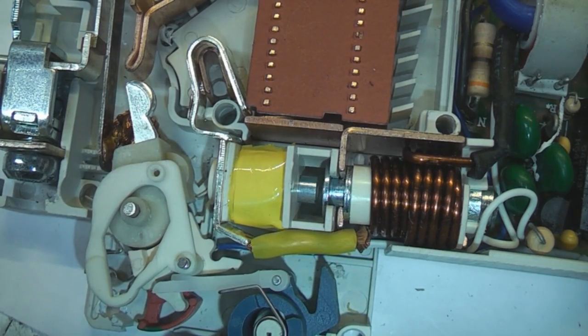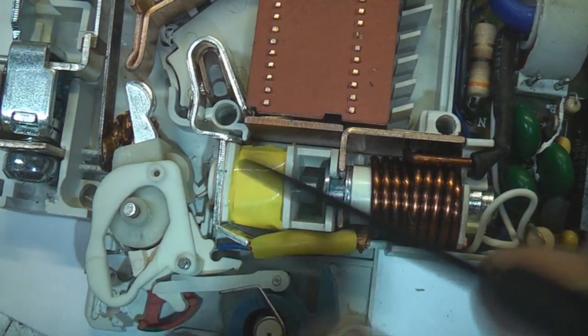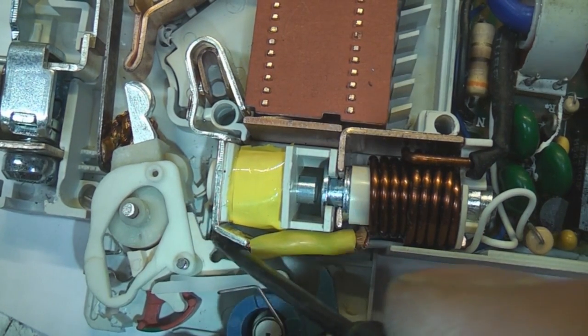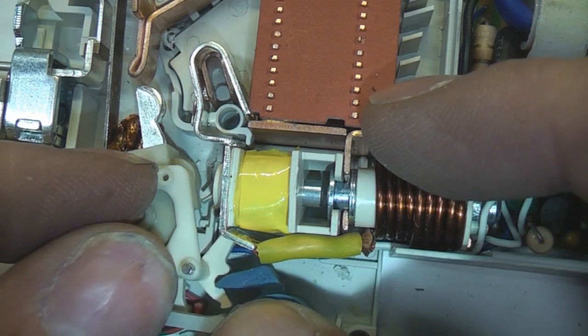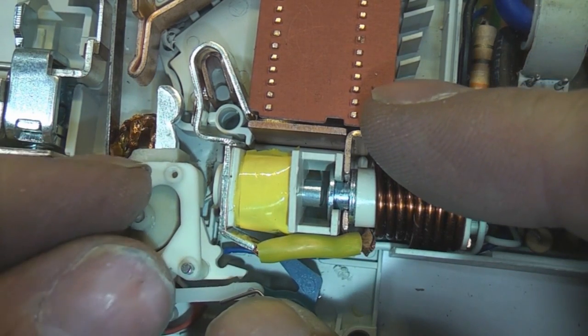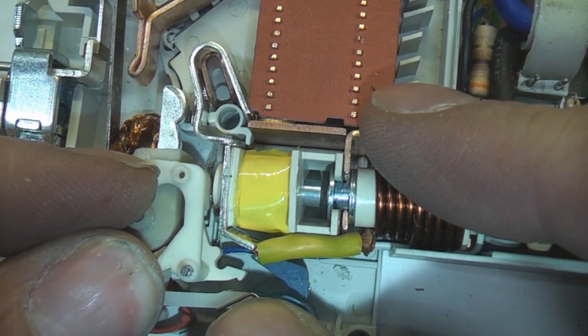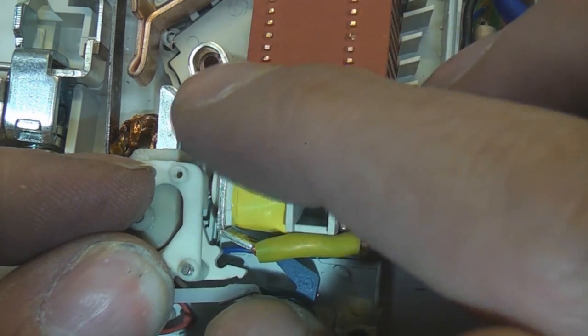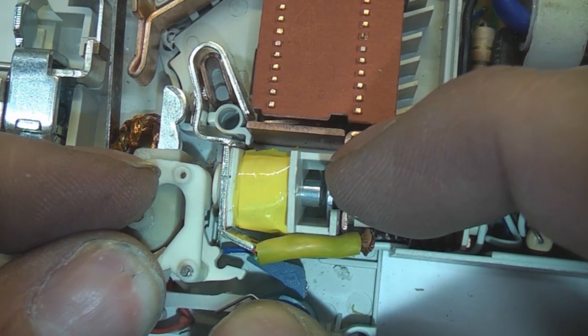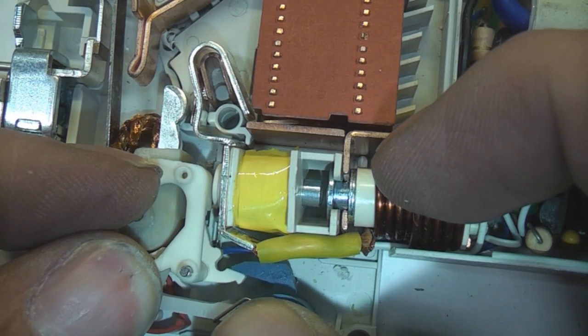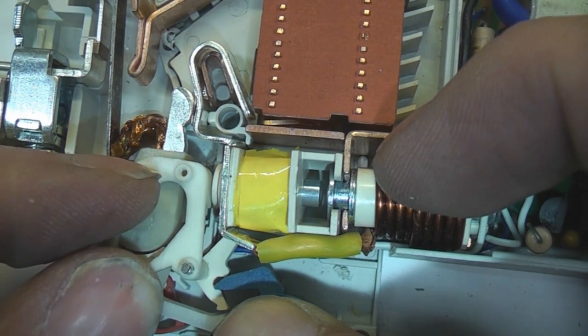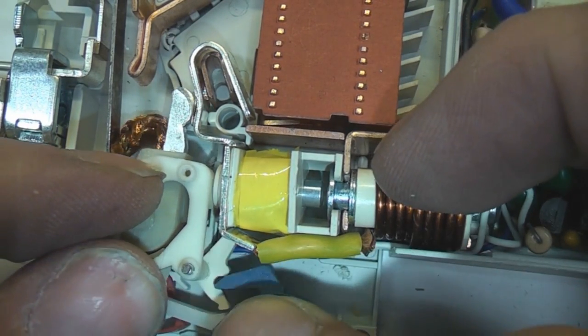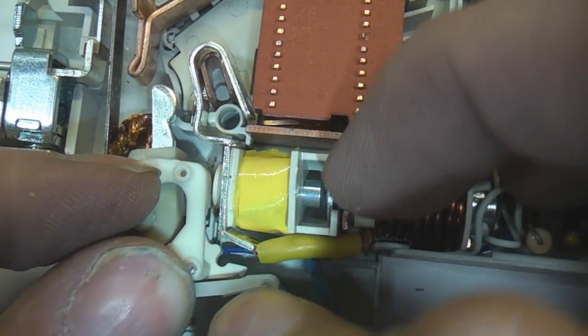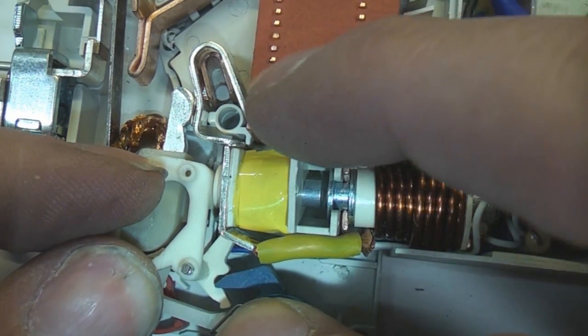I just actually noticed when I was putting this back together, there's a little piece missing. This little piece here, what this does is just... close it. You see the contact starting to close, but then it pauses until the switch is all the way in, and then it suddenly snaps down. So any small amount of arcing you get when the contact closes, it minimises that time to avoid the risk of the contact welding shut.